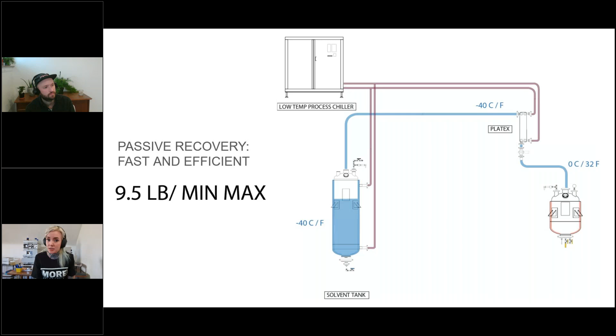Whereas with a pump, you can run that pump until it breaks itself, or you can run that pump in a way that you break it. And it's very common. I know a lot of people were running the pneumatic pumps for a while, and that was exactly the issue they ran into: a lot of constant rebuilds because they were pulling under vacuum. So if you don't see positive pressure on that collection vessel at all times, first of all, you have other problems we'd love to help you solve. But second of all, you're killing your pump. Your pump hates you if that collection vessel is at zero and you're pulling down to a vacuum. So it's just not suited for what most people are applying it towards.